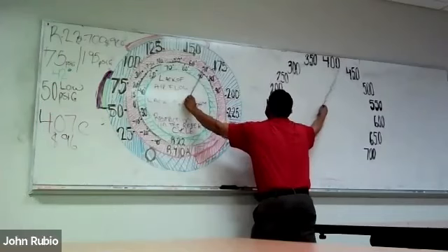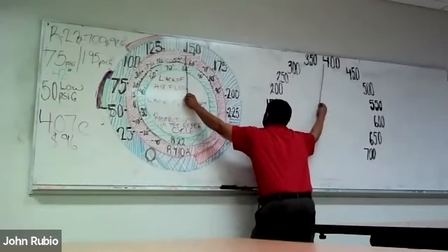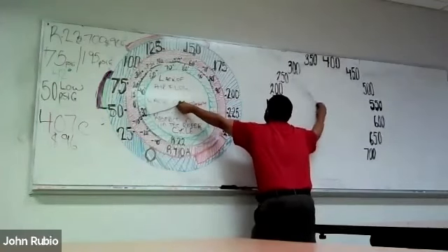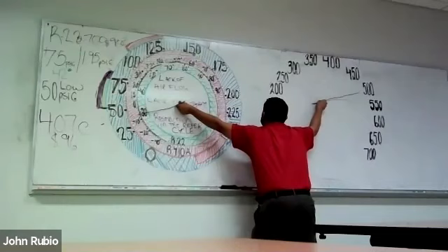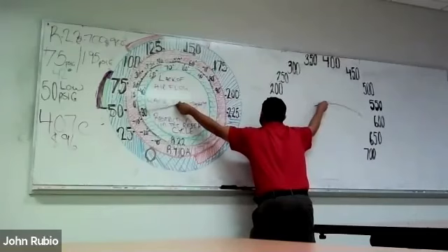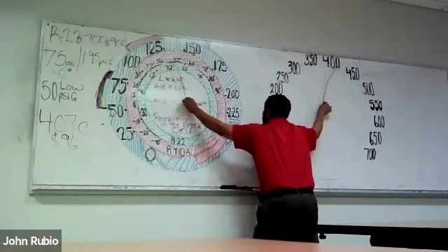Again, if you find low refrigerant, you need access to your high side. I need the congruency of this needle to confirm or deny. Confirm we truly are low and we're not restricted, or tell me I am wrong and I'm about to waste refrigerant and make a fool out of myself because I am not paying attention to congruency of needles.